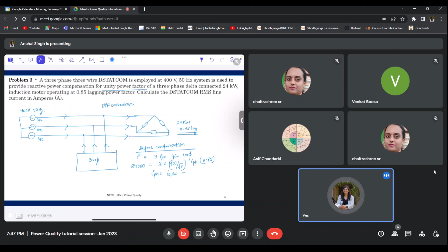Before compensation, P active power is equal to 3 V phase, I phase, cos phi. Active power is given as 24 kilowatt, that is 24,000. 3 into V phase, which is 400 by root 3, since V line to line by root 3 is V phase. And I phase is the one which we want to calculate, and cos phi is 0.85, right? So I phase, which is equal to IS new. Sorry, IS old, that means before compensation. This is IS old. It will come out to be 40.75 amperes.